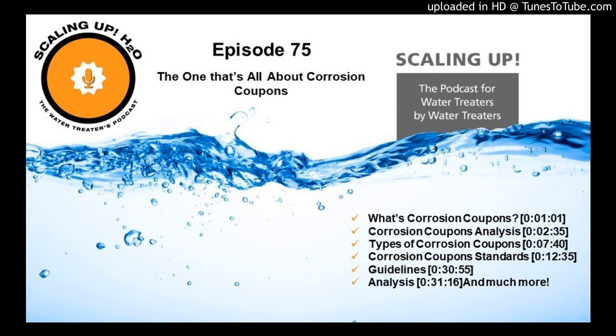Now, if we only have that coupon in there for 30 days, a lot of those days will be indicative of that higher corrosion rate. So if you're only using 30-day coupons, expect your corrosion rates to be a little higher than they actually are in the system. So how long can you leave corrosion coupons in the system? Well folks, you can leave them in as long as you want, you just have to make sure you know the original date you put them in so we can run the calculation. Again, the longer they're in there, the more indicative they're going to be of the system you're trying to gauge the corrosion rates for.